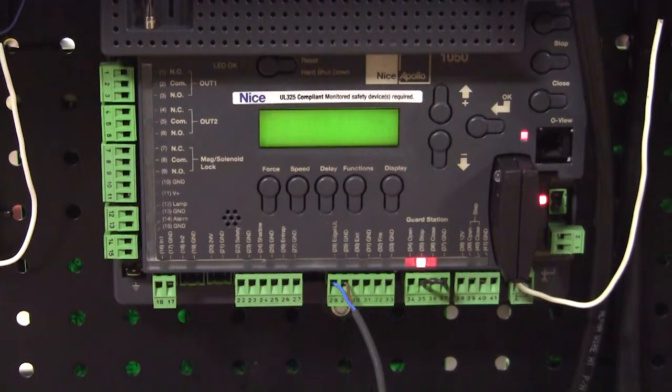It's going to scan the blue bus. It's looking for my one monitored entrapment device, at least one. In this case it's going to find the UL or find the 10k resistive edge.